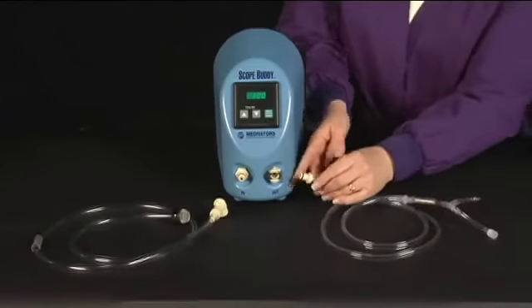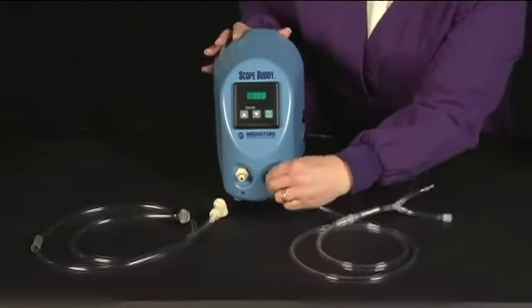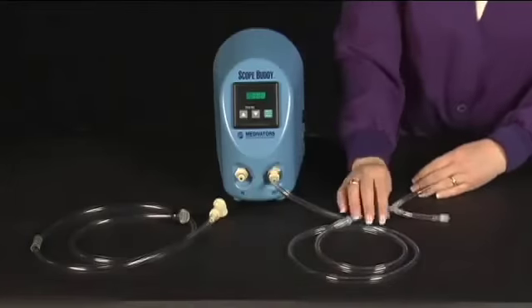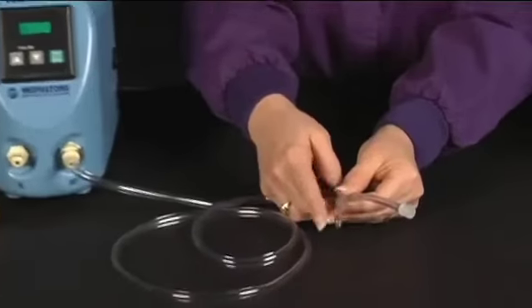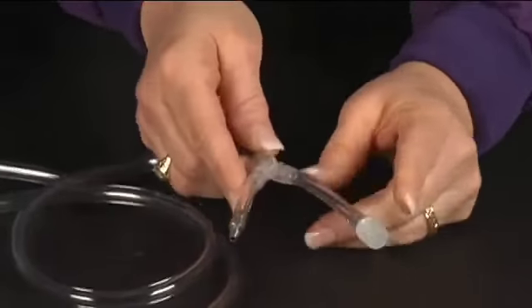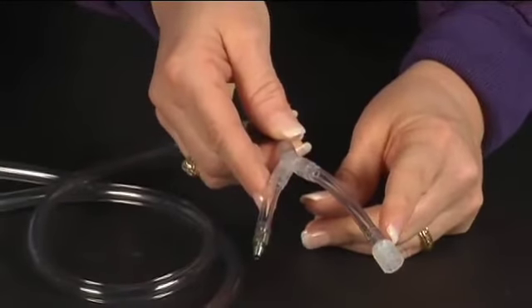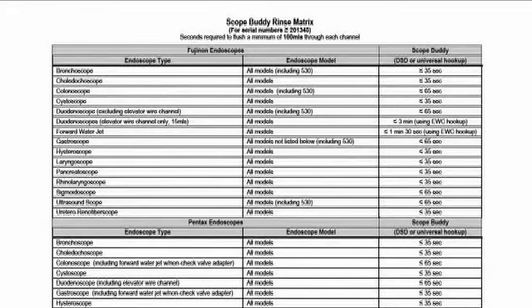Then the DSD extension line is removed and the elevator wire channel hookup should be snapped into the port labeled out. The other end has a metal port that remains open and the luer lock connector attaches to the endoscope's forward water jet or elevator wire channel. Reference the Scope Buddy rinse matrix to set Scope Buddy to the required time to flush the elevator wire channel of a Fujinon duodenoscope or the forward water jet channel of a Fujinon endoscope.